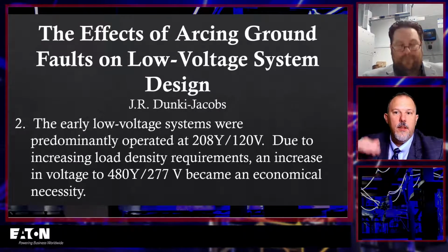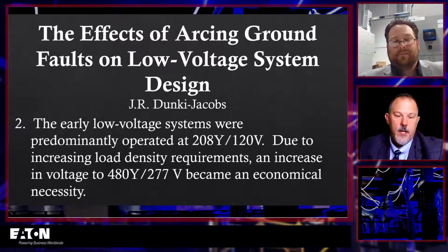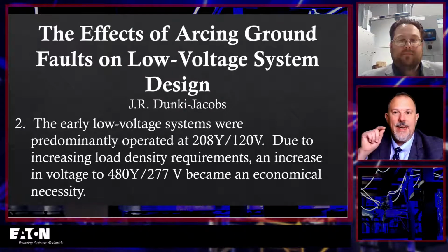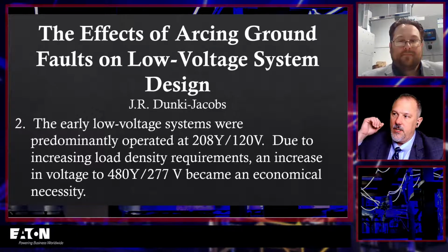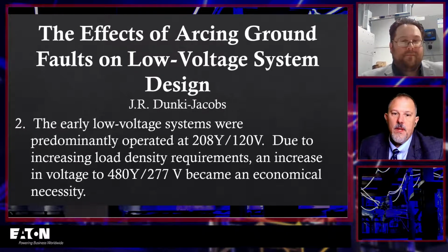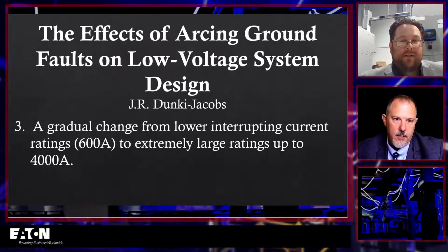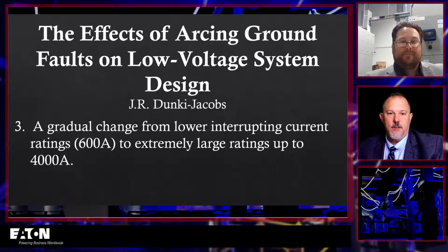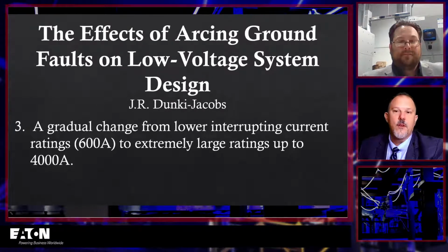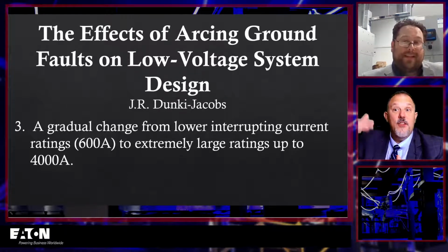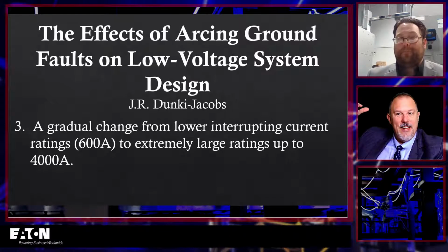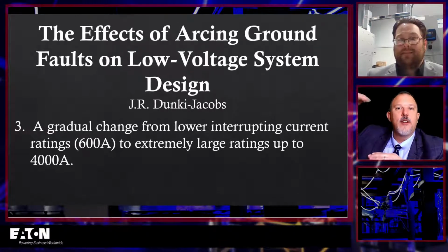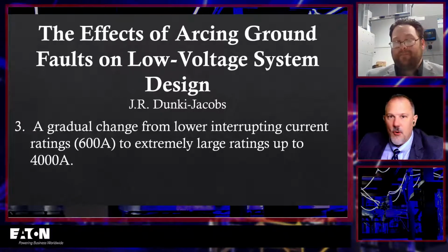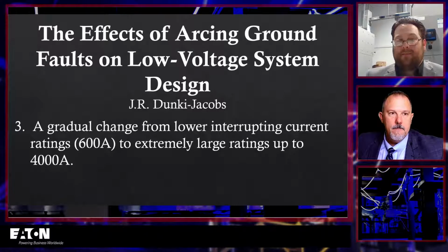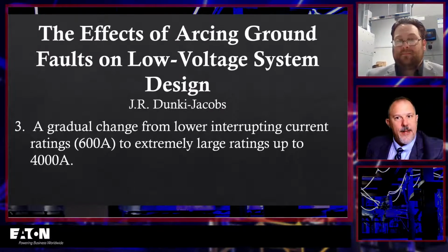If you think about a transformer, the primary full load amps is less than the secondary full load amps, as long as the primary is higher voltage than the secondary. So we went from an ungrounded to a grounded system, which means I have higher fault current. I have that first fault current is a doozy, right? There's no gimmies there. I went from a lower voltage to a higher voltage, which means I have more pressure. And then the average service went from 600 amps to 4,000 amps. Because the voltage went up, my currents are going down, right? So now, at the higher voltages, I can have larger ampere services, and I transport my power across because of the load density issues going on. And you have the perfect storm for an arc flash.